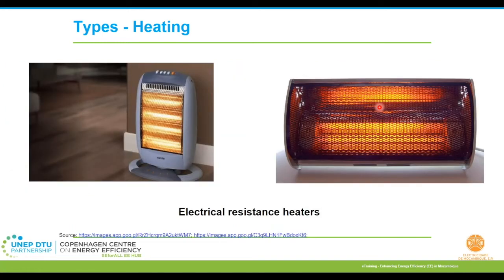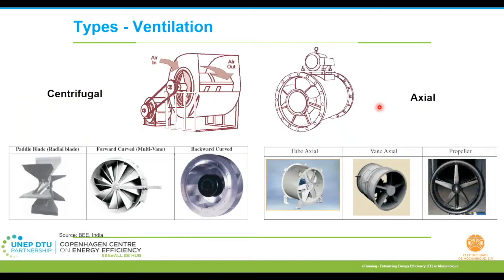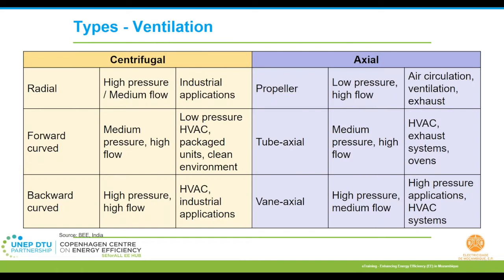And then you have these electrical resistance heaters, mostly portable ones and all, which are conventional. For the ventilation types, the major components are fans and blowers. This slide gives you different types of fans and blowers that may be used for various applications, depending on the flows and pressures that one is working with. Of course, the radial blade is not a common one, but the remaining types are often the most commonly used types for HVAC systems. You can see here, based on the flow and pressure requirements, the applications vary for different fan types.